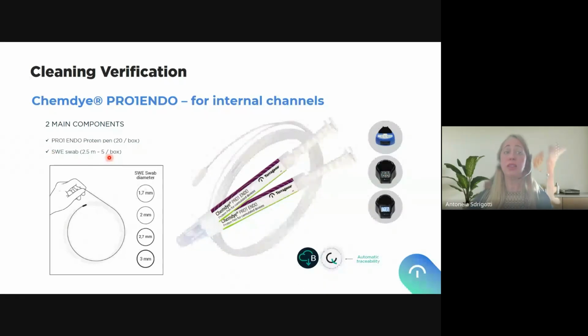The swabs come in 4 different options, offering 4 different sizes for different internal diameters, all of them 2.5 meters long. The sizes are 1.7, 2, 2.7 and 3 millimeters. This is the size of the head of the swab. With the swab you take the sample, and after you activate the pen, you put the swab in and incubate 4 minutes or 7 minutes in exactly the same way, because the reaction is exactly the same. Same devices, same technology, but a dedicated product for verification of protein residues inside the channels.